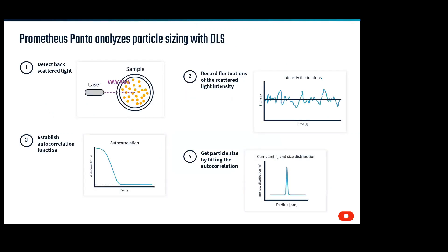Finally, we're excited to now offer DLS in tandem with these technologies. The DLS optics work by measuring the intensity of signals scattered at an angle from the sample. This intensity fluctuates based on the movement of molecules, which is ultimately related to the size of the molecules. We use an autocorrelation function to correlate these intensity fluctuations over time to the size of the molecules in the solution. The result of the autocorrelation fit is a measurement of the hydrodynamic radius of the particles in solution.